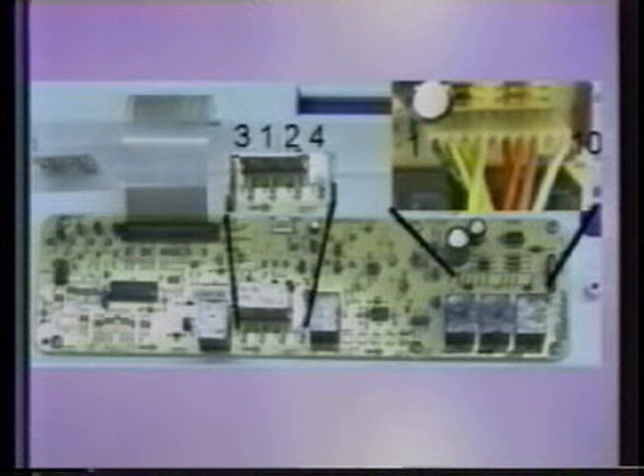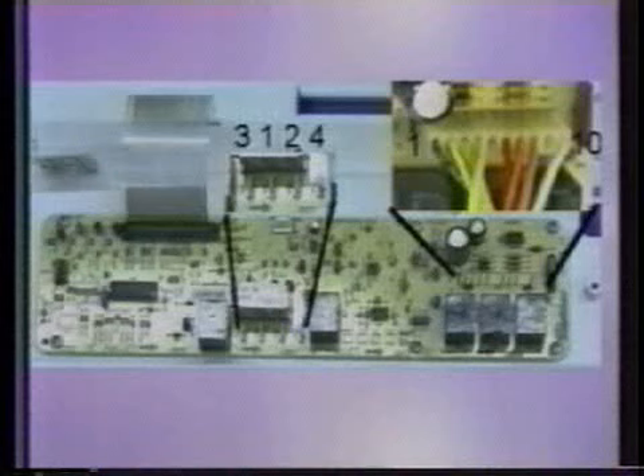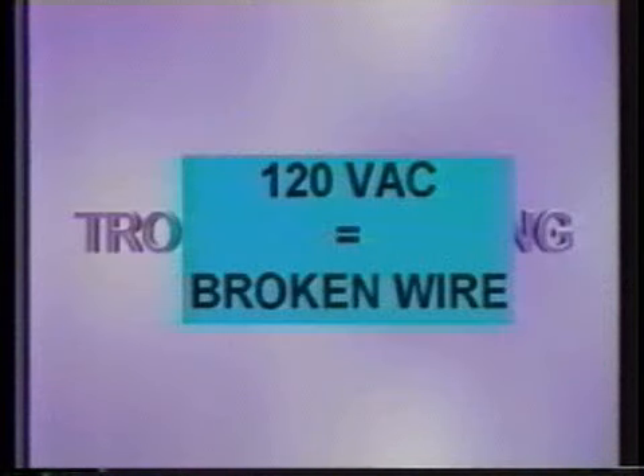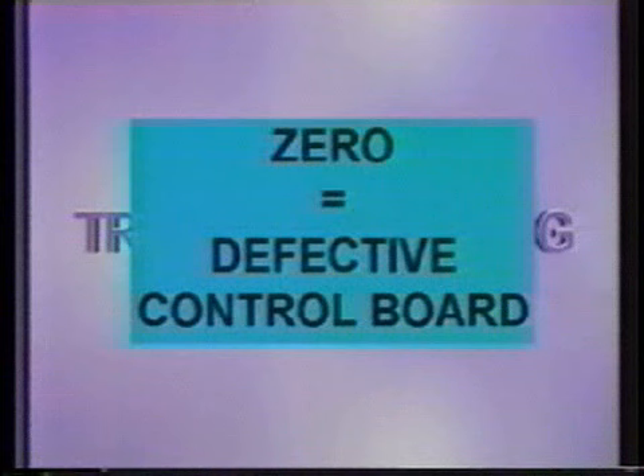If I have 0 volts, I have to go back up to the control board and measure the output voltage between terminal PT03 and neutral. If I have 120 volts here, I know I have a broken wire between the control board and the wash pump. If I have 0, I know I've got a defective control board.